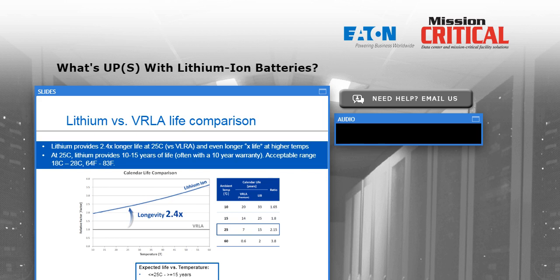On the horizontal axis here you see temperature in degrees Celsius, and on the vertical axis this is not years of life, it's something called a relative factor. At 25 degrees centigrade, roughly room temperature, the VRLA relative factor is 1.0, and the lithium factor is about 2 to 2.5 times that. So if valve-regulated lead-acid were a 5-year battery, the lithium battery replacing it would be at least 10 years of service life at that temperature.